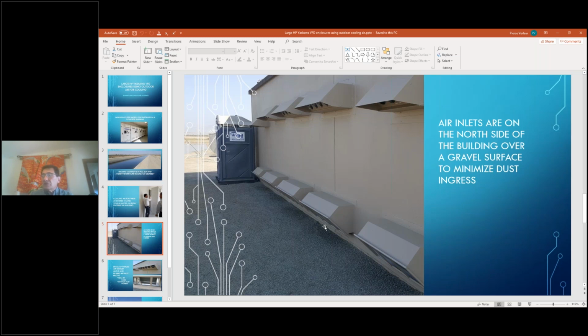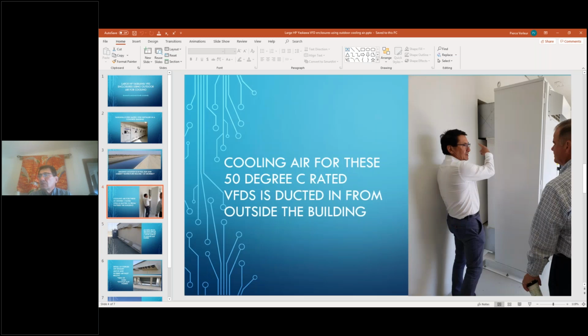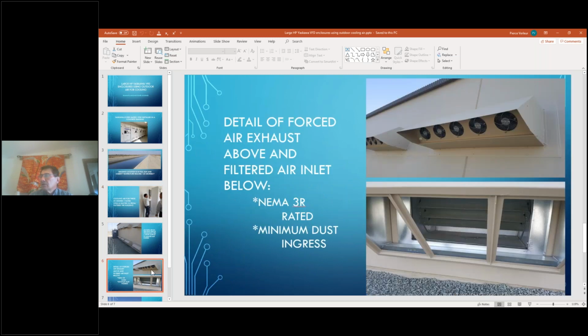And these hoods are the standard hoods that come with the drive. The cost adder was to put these ducts in play. So we had a little bit of sheet metal cost. For that investment, we maintained the good environment that the drive is rated for. Certainly we've proven that in the agricultural world. And we reduced significantly the building cost. Here's the detail on the hoods. You can see in the bottom, those are our air inlets, and these are our forced air outlets at the top.